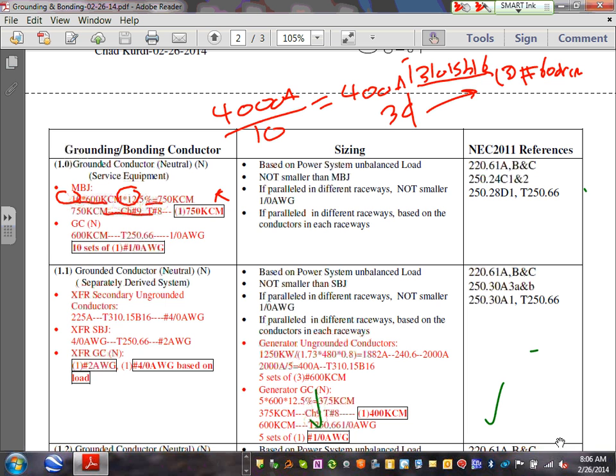We're parallel. So when you parallel, you apply this rule. If you look at this rule, it says when you parallel, when you size a conductor, take the largest ungrounded conductor, go to table 250.66, and size it based on 250.66, and that will get you 1/0 AWG. So gentlemen, your neutral conductor cannot be less than 10 sets of 1/0 AWG. Any comments, any questions? So that's how we size the neutral conductor.